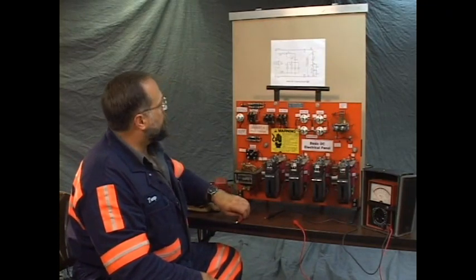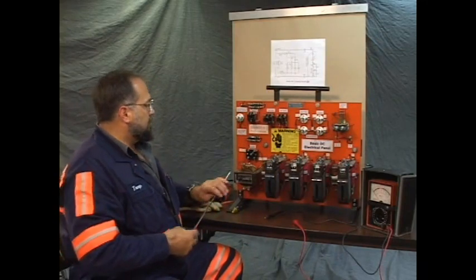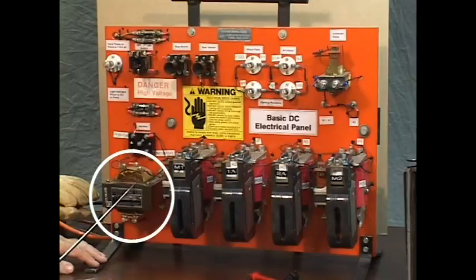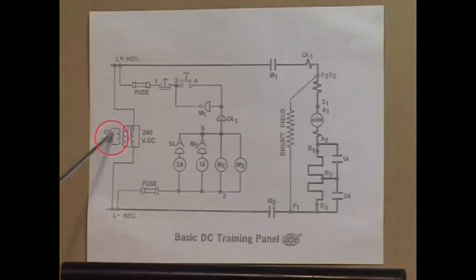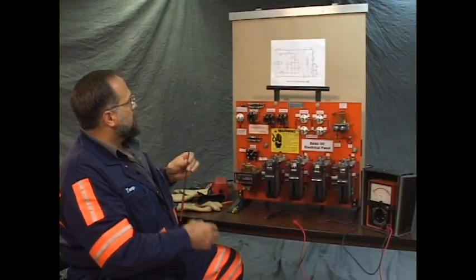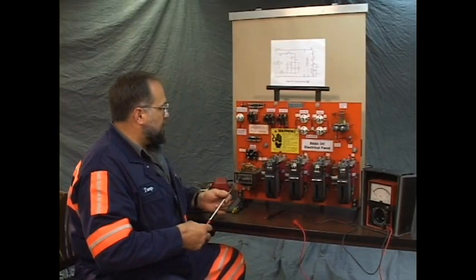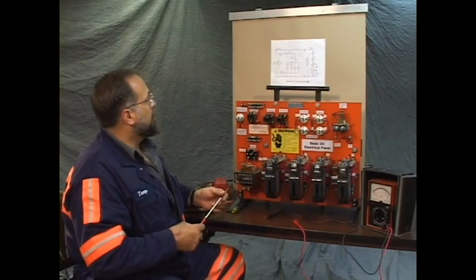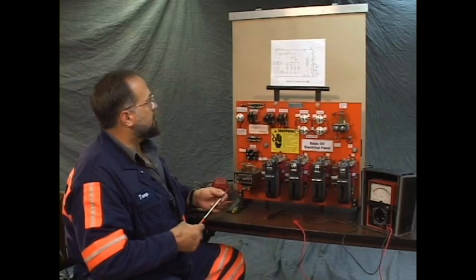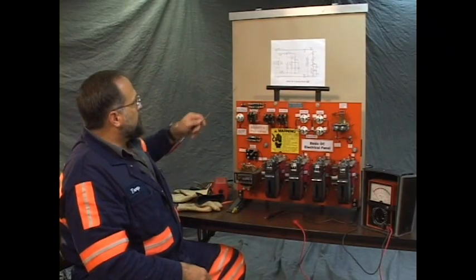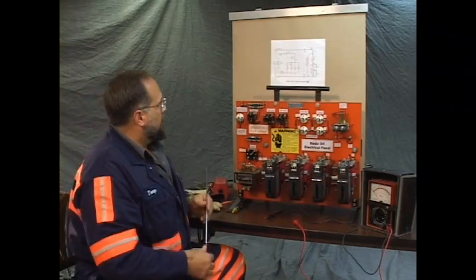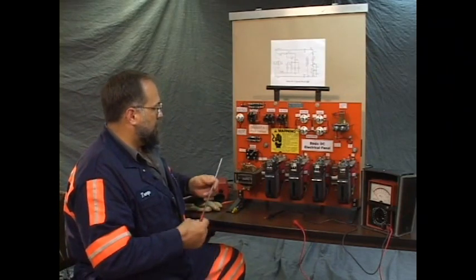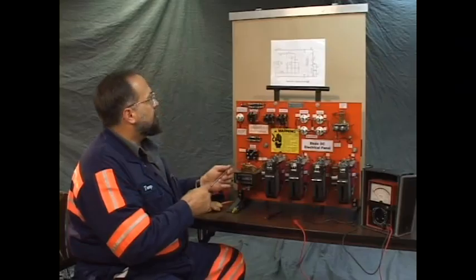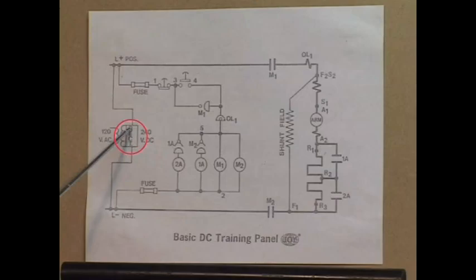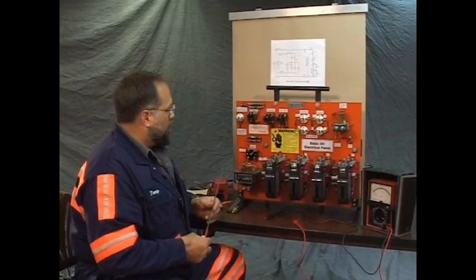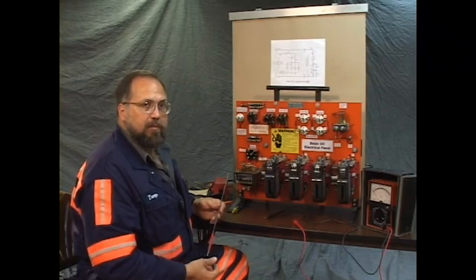Okay. First part that we're going to identify on the panel is the control transformer. This is the control transformer, and on the print this illustrates the control transformer. Note that this is a step-up transformer. It can be used in either way, but in this application we're stepping up from 120 volts to 240. Control transformer. The next part in the circuit is the rectifier here, and on the schematic it's here. It's the rectifier. This is the point where we change the AC power supplied to DC.